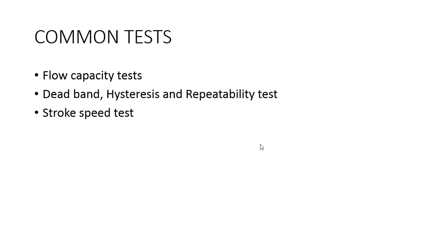There is a standard, ANSI/ISA S75.02, that is used. Acceptable accuracy is within plus minus 5% of the maximum CV. One can calculate FL and XT factor which are used for choke flow condition for liquid and gas.